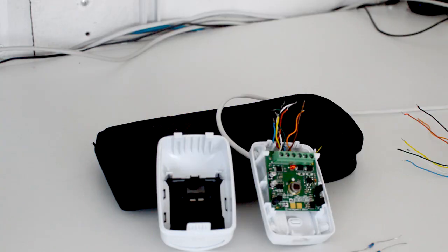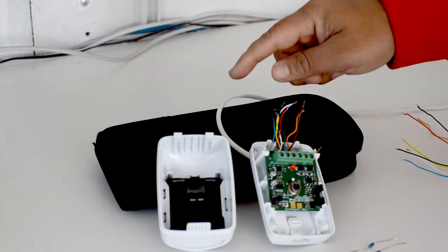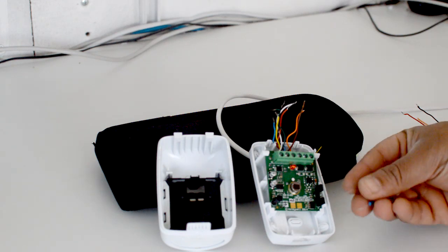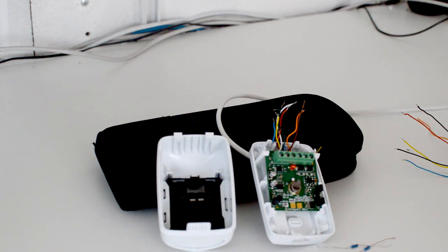In this video segment we're going to show you how to install a basic passive infrared detector. Now we're going to see how to wire a PIR. This is a Honeywell PIR grade 2.1. What I have here is Honeywell grade 2 PIR alarm cable and resistors. I'm using 1k resistors here.